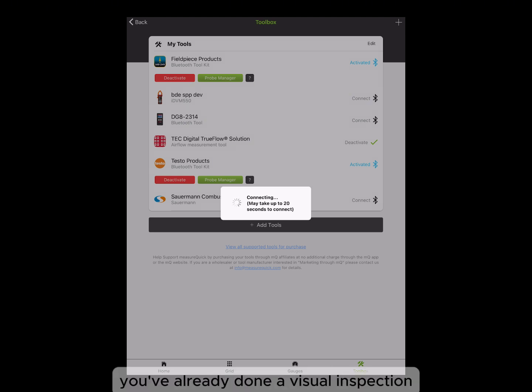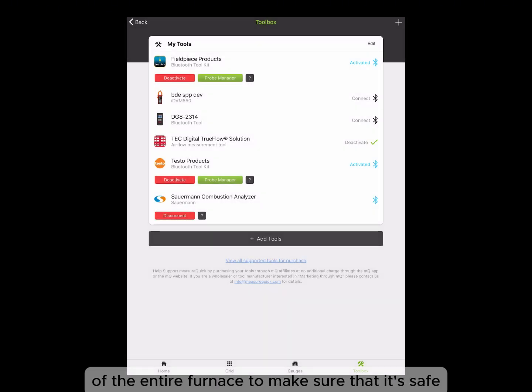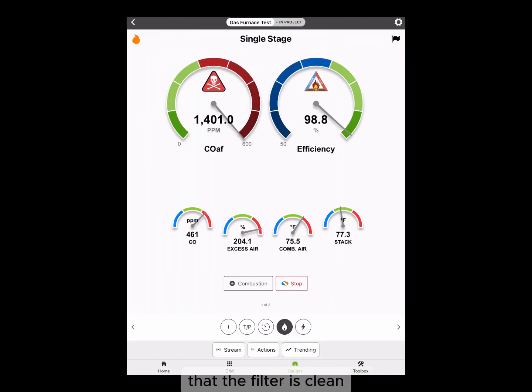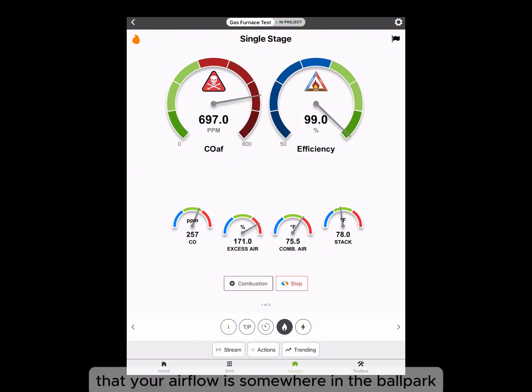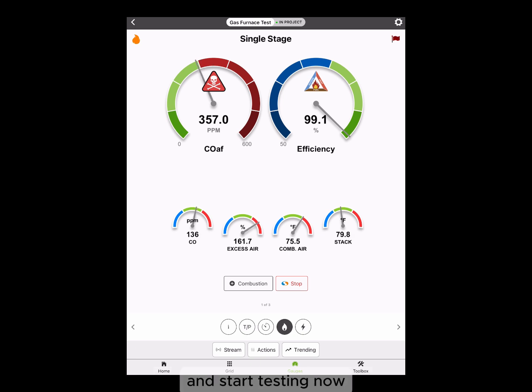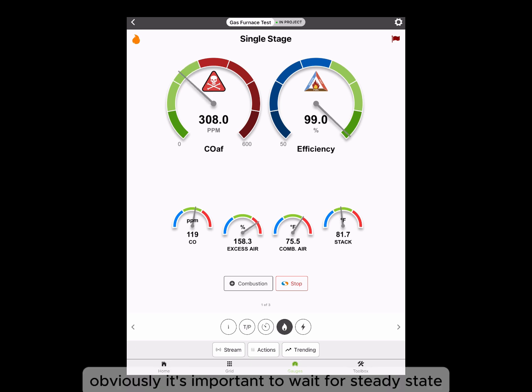Now, by this time, you've already done a visual inspection of the entire furnace to make sure that it's safe and that there's nothing glaring that's jumping out at you. You verify that the blower wheel is clean, that the filter is clean, that the ductwork is in good shape, and through static pressure, you verify that your airflow is somewhere in the ballpark. After calibrating the combustion analyzer outside, you're then going to insert your probe and start testing. Now, obviously, it's important to wait for steady state, which is going to take around 10 minutes.